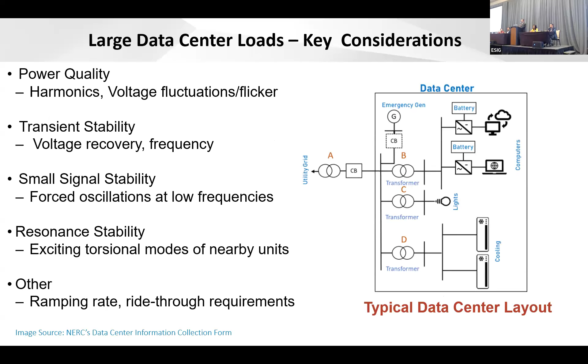So we get that information, and then we look at, for a 1 gigawatt load, what percentage is IT load versus cooling load. This matters because IT equipment is very sensitive to voltages and even frequencies. If there's a system disturbance nearby and the system voltage drops, the IT load can switch over to local emergency backup generation, typically diesel. But from a system perspective, it's like you lost that load, so it becomes super critical.